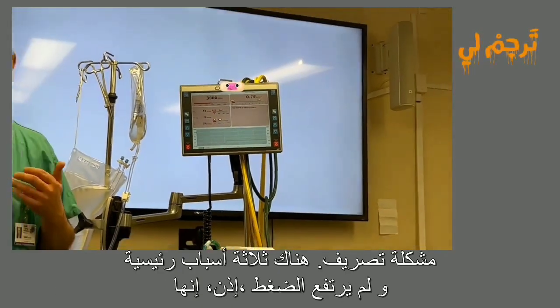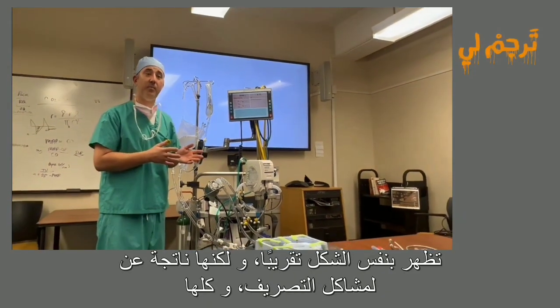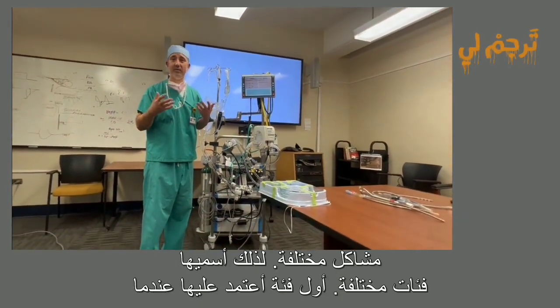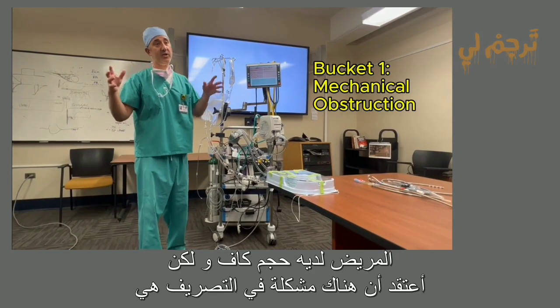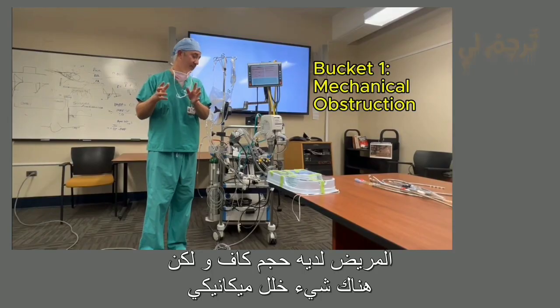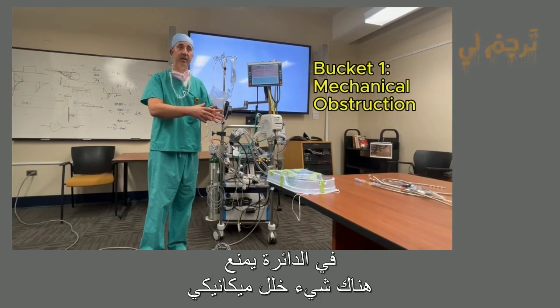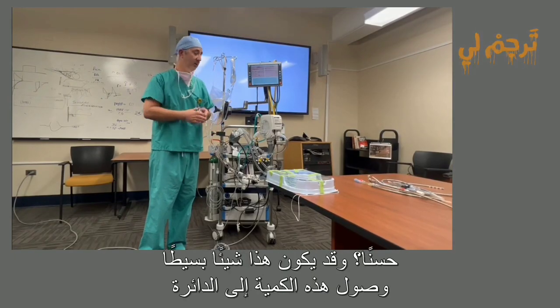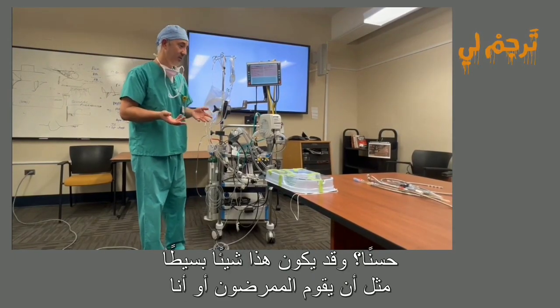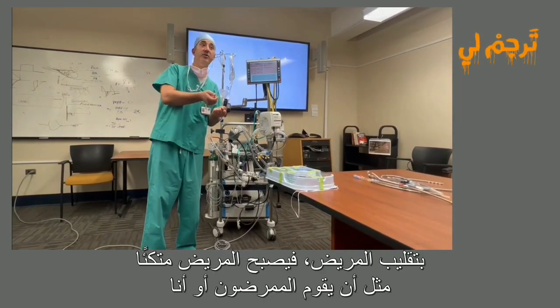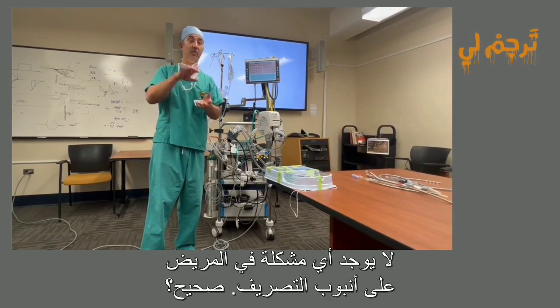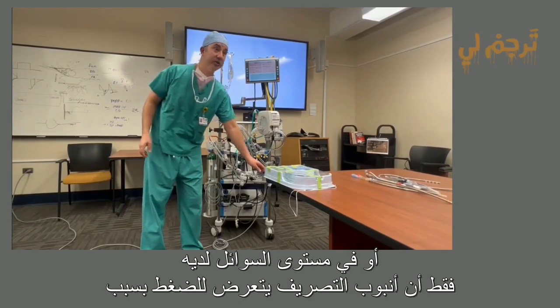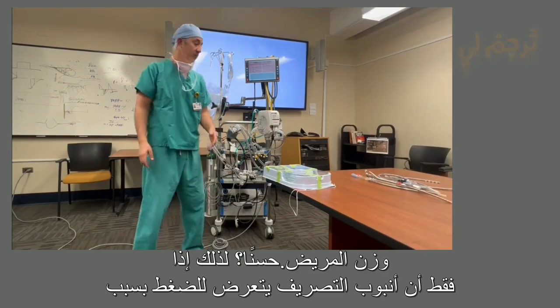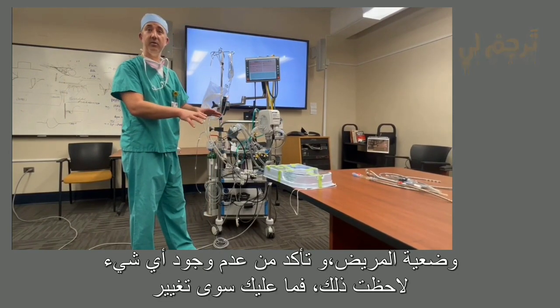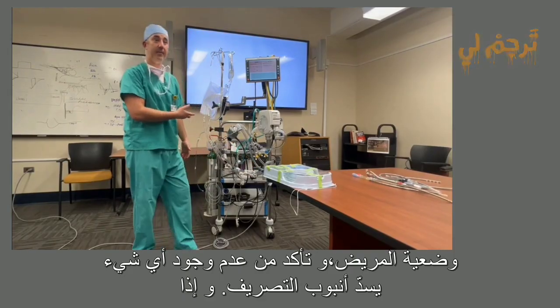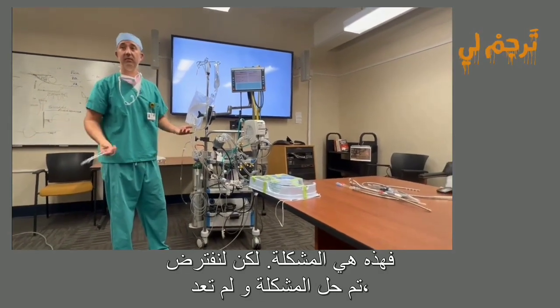There's three major causes of drainage issues that all kind of present the same, but are caused by different issues. So I call them different buckets. My first bucket, when I think there's a drainage issue, is that the patient has enough volume, but there's something mechanically wrong with the circuit that's preventing that volume from getting into my circuit, okay? And that could be just something as simple as the nurses or I turn the patient, and now the patient is leaning on their drainage cannula, right? There's nothing wrong with the patient or their volume status. It's just that the drainage tubing is getting compressed by the weight of the patient, okay? So if you notice that, just reposition the patient, make sure there's nothing obstructing the drainage cannula, and if that fixes the problem and it doesn't come back, that was the issue.